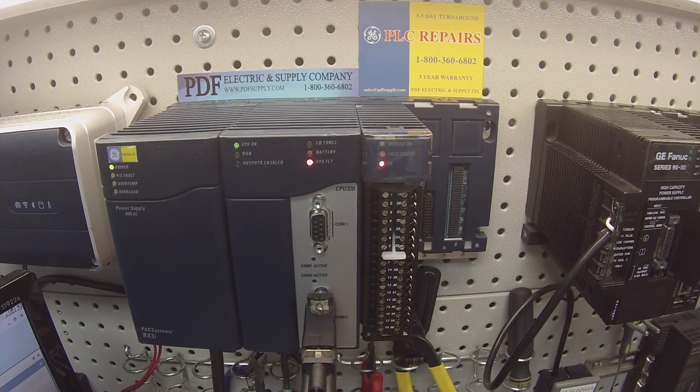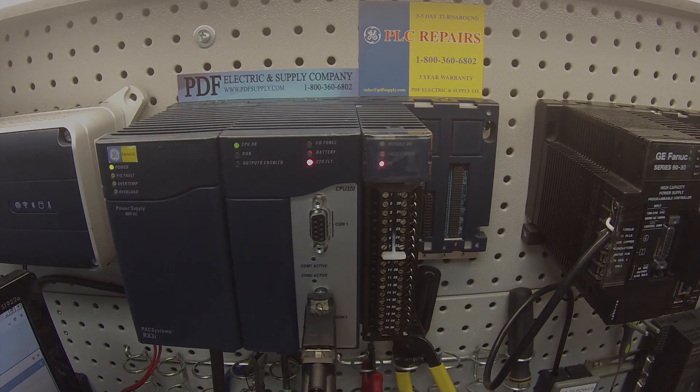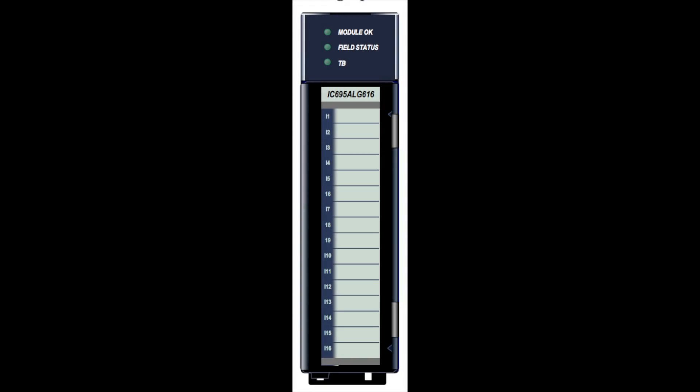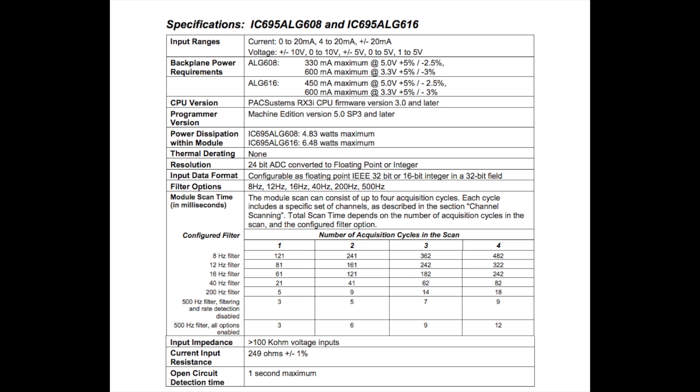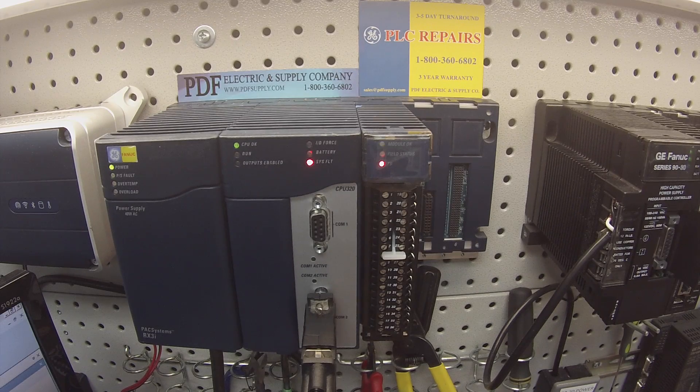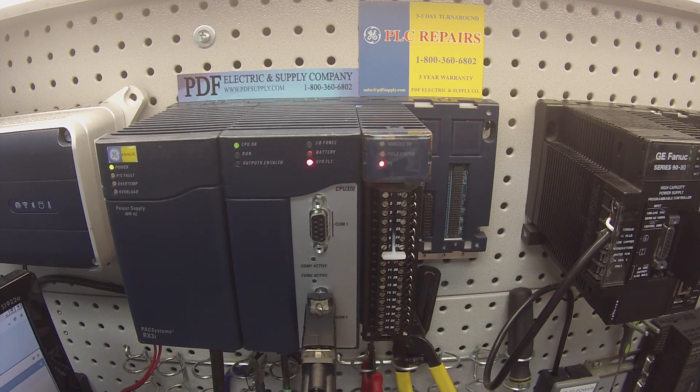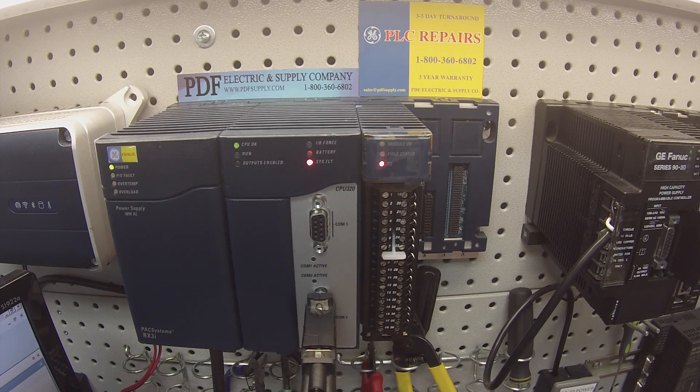Hello and welcome to PDFsupply.com. Today we're going to be testing an IC695ALG616. This is a 16 channel single ended voltage or current DC analog input module. Voltage ranges from negative 10 to positive 10 volts DC, and current is measured in 0 to 20 milliamps DC. I'm going to show you how to test this and how to troubleshoot it.